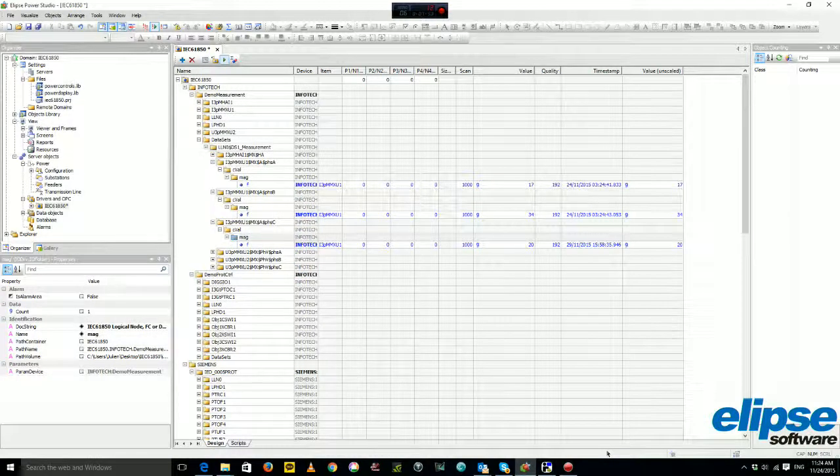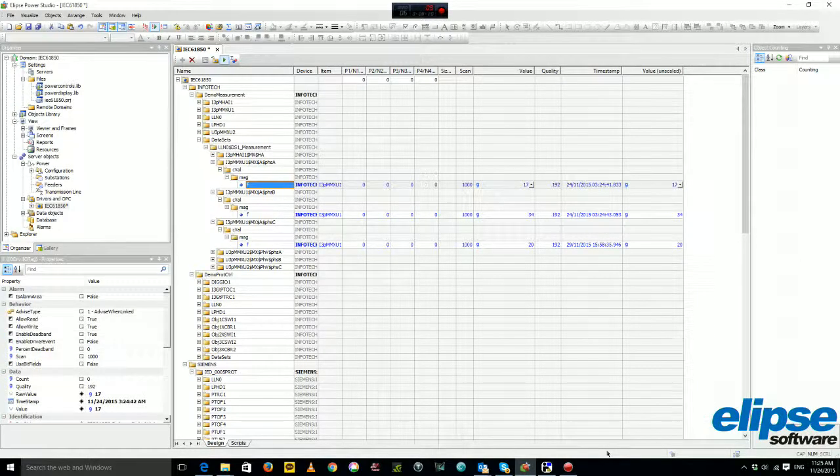maybe it's because the IED is not well configured. If the configuration of the IED is wrong, if the IED has wrong settings for the control block, if the IED doesn't have a control block for each dataset, then you will not be able to read this tag.